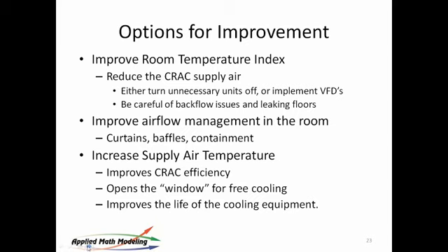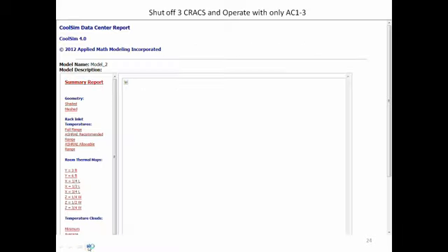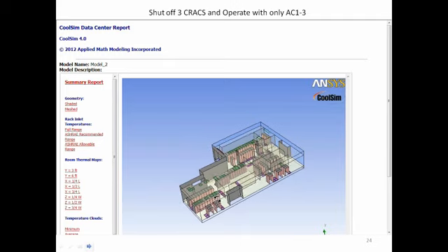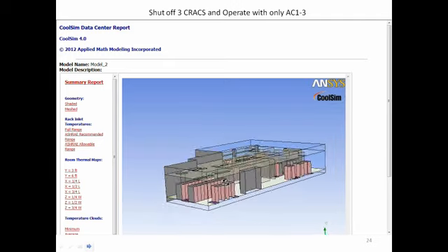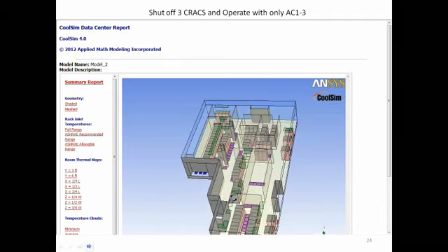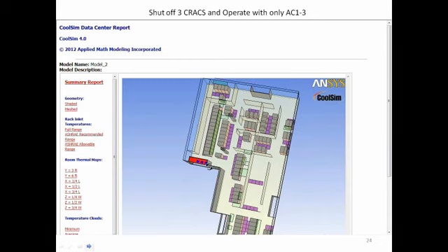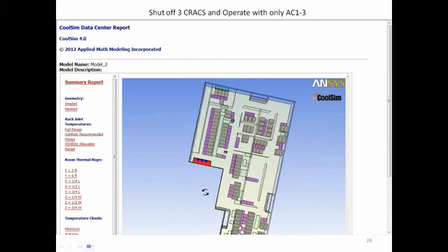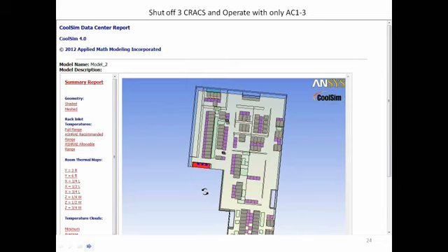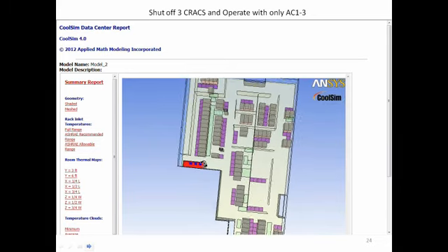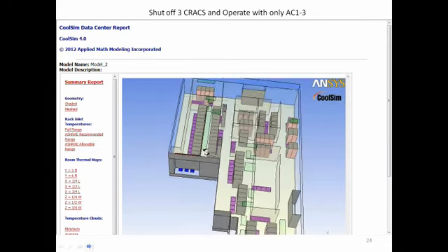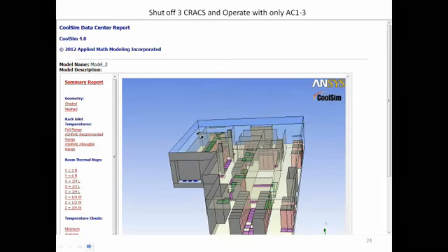And if you're using any kind of free cooling at all, it's going to open the window for that tremendously, and your COP will go way up. And it's going to improve the life of your cooling equipment by getting it to run only when it needs to run and run in its design center. So the first thing we did on this particular model is turn units off. Here, if you look, there's only one unit on now, and that's the one over near the load. The load is highest over in this part of the room. So we left this one on, just to see what would happen.